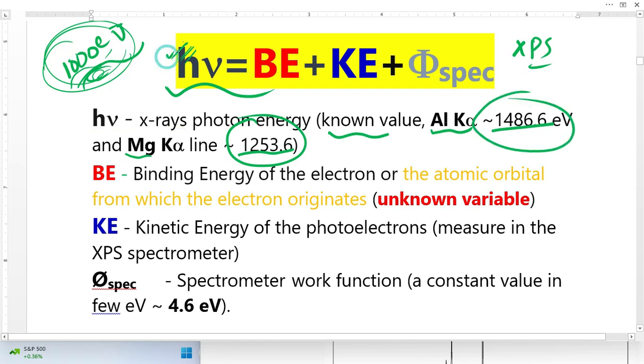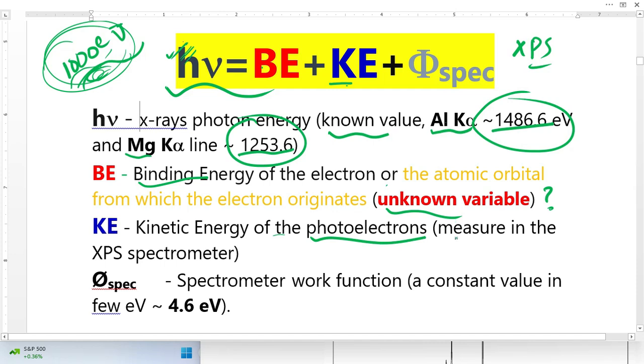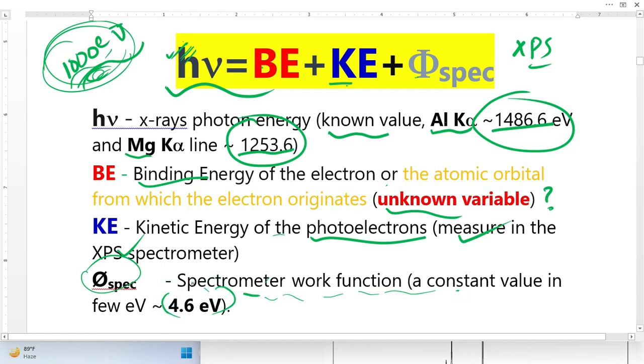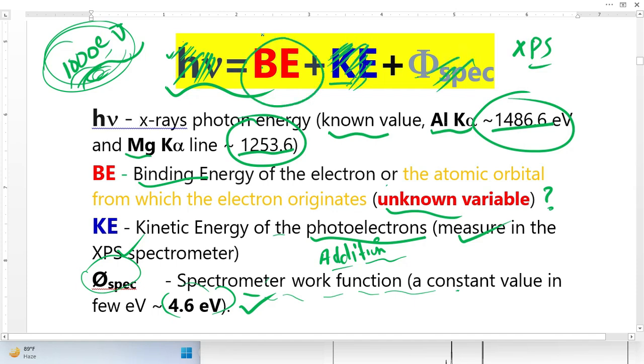This is why we use these two types of sources. The binding energy is the binding energy of electrons — it is unknown and we have to calculate it. The kinetic energy refers to photoelectrons, not Auger electrons — this is what the XPS spectrometer measures. The work function for the spectrometer is a constant value; in most cases it is 4.6 eV — the additional energy required to take electrons from the spectrometer surface. Since X-ray energy and work function are constant and kinetic energy is measured, we can easily calculate the binding energy.